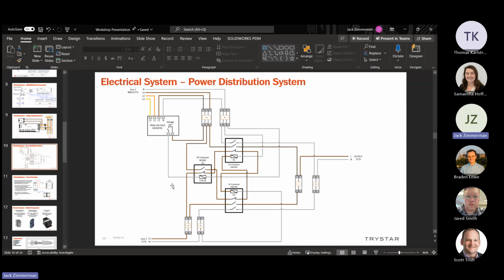So is line one supplied by source one? Correct, yes. And the same for line two? Correct, source two. So when you have a generator, it sounds like the way you set up the sources here, it always favors line one regardless of whether it's utility or a generator. Yes, it will, whichever one you wire to line one. Remember that these wires can be swapped to switch them, but yes, in the circumstances wired here, it favors line one.